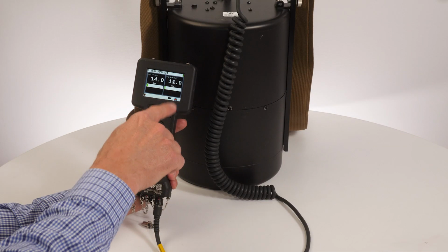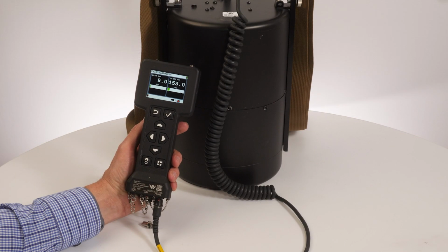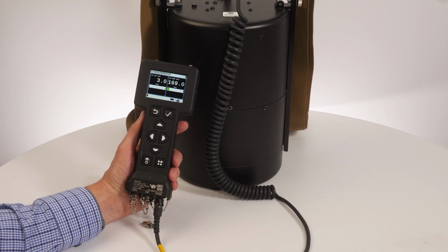Before starting your survey or mission, you should verify the probe is working as expected by performing a source check. For the source check, ensure the 13 to 220 keV channel is displayed on the home screen. If it is not displayed, press the Enter key until you see it in the right radiation reading panel.